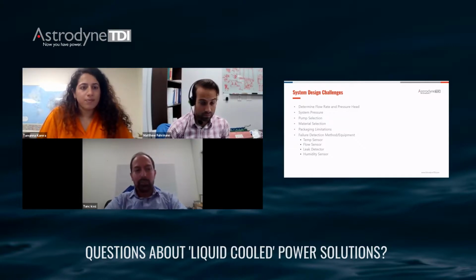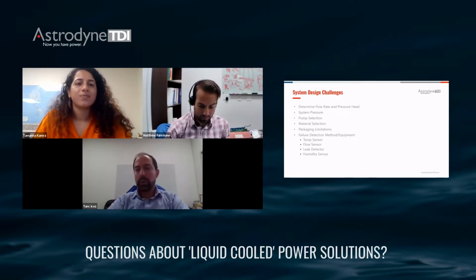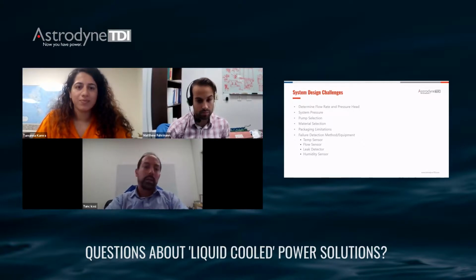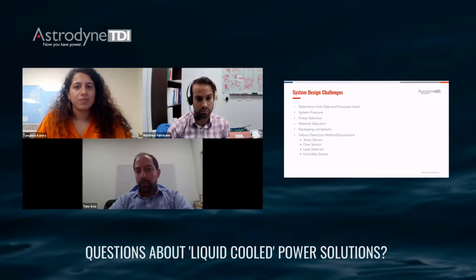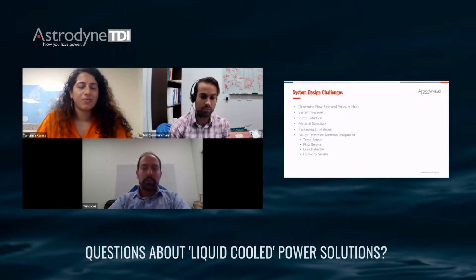I'm sure every engineer has a different opinion on this, but to me, the biggest challenge is identifying the flow rate requirements and the pressure drop. That impacts the configuration. Like I said, I think that's the fun part. You solve the puzzle, you put the pieces together, and then try to optimize the system. System pressure and flow rates basically equate to the pump selection. What are the pumps available? How much power do they dissipate? How big are they going to be?